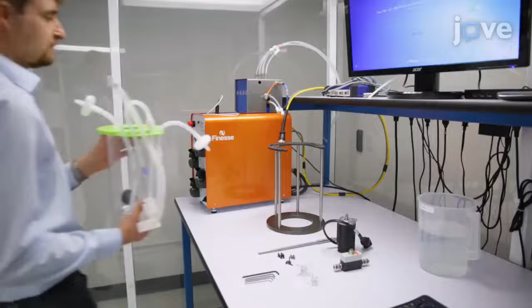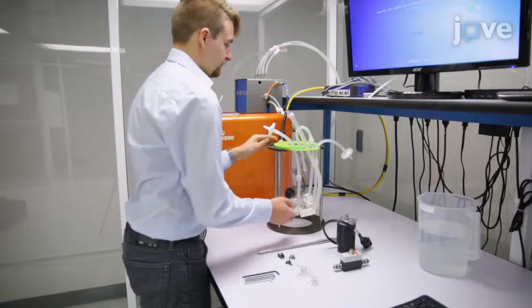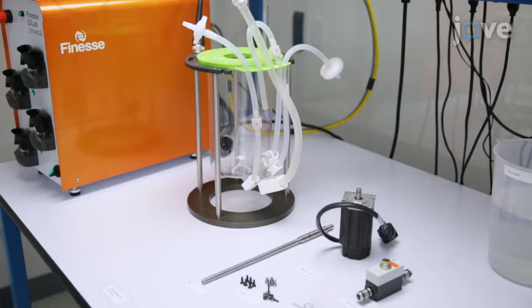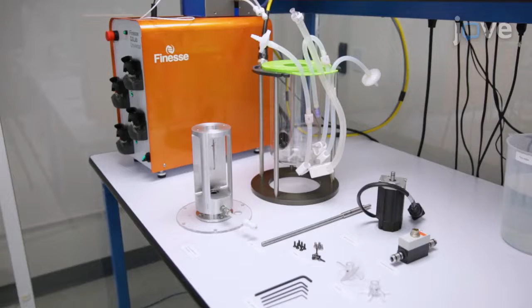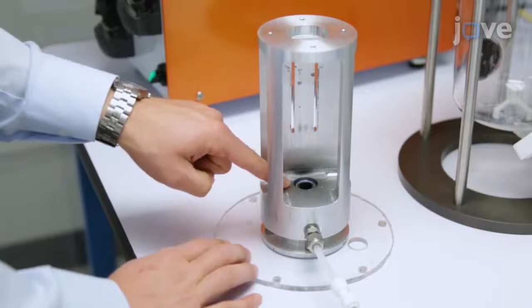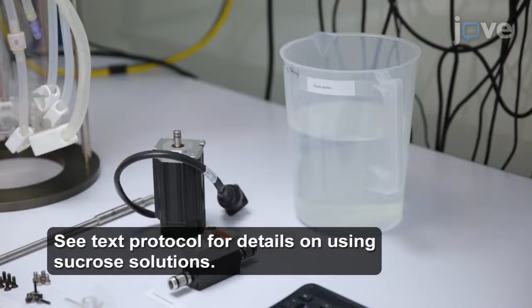Set up the bioreactor elements and control apparatus on a lab bench. For this experiment, there is a 2-liter mixing tank and the vessel holder. There is also a specially designed holder for the agitator motor, and in addition to a mount for the motor, there is a mount for a torque meter. The special design includes an air bearing with an input for pressurized air. Use a computer and bioreactor control unit for data acquisition and control. Also, provide a liquid with defined density and viscosity, such as pure water or sucrose solution.